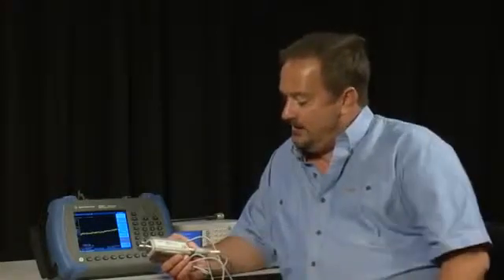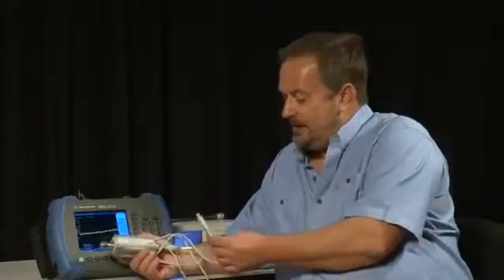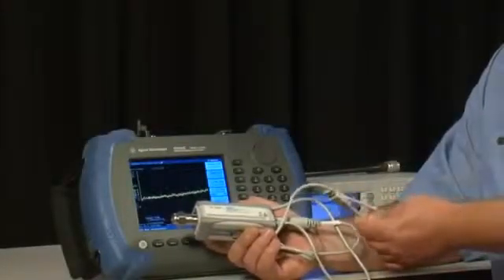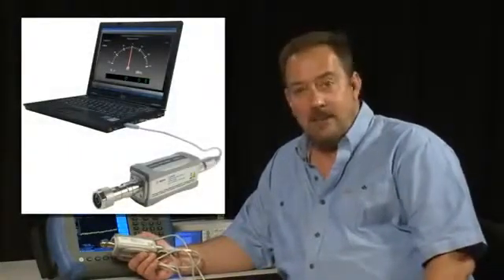If you've got one of these Agilent U2000 series USB power sensors, you'll know that it's not only a power sensor but a complete power sensor and power meter all combined in one unit. The connector on the end is a USB plug rather than a normal power sensor connector, so you just plug the unit into your laptop PC and it converts it into a microwave power meter.